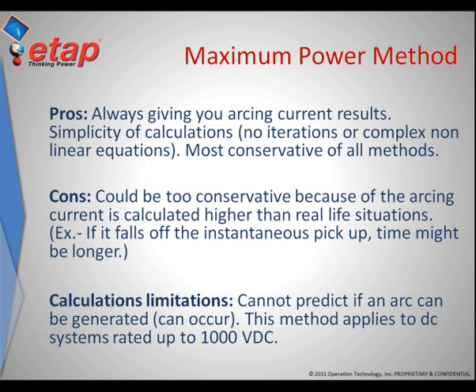The simplicity of the model is what is most beneficial about the maximum power method — it should always give the user results because it is based on the fundamental maximum power theorem. It also provides the user with the most conservative results of the three available methods within ETAP. The con behind this method is that it may not yield an accurate magnitude of the arcing current and will not reflect an accurate operating time of protected devices. Also, it has not been tested or validated for systems rated higher than 1000 volts DC.